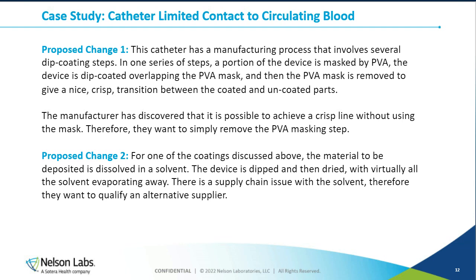So we have a catheter that is manufactured with a process that includes several dip coating steps. So anybody that's in the catheter business knows that typically there's a lot of dip coating. And then in one series of these steps, a portion of the device is masked by polyvinyl acetate. The device is dip coated in a way that the new coating overlaps with the mask, and then later the PVA mask is removed to give a nice crisp line between the coated and the non-coated parts, right?